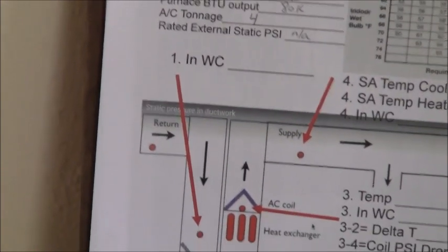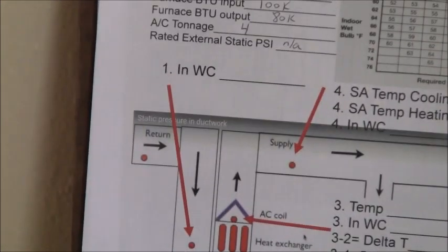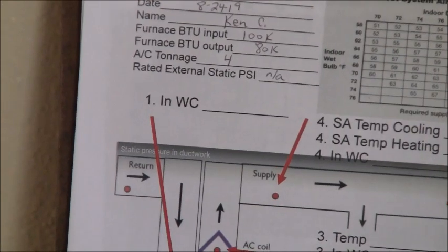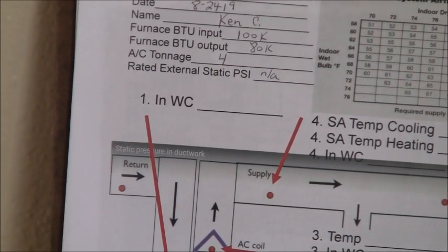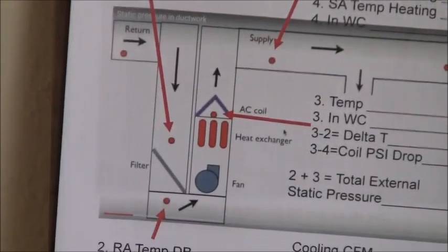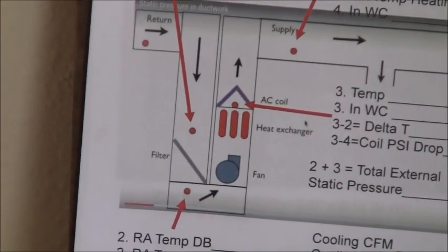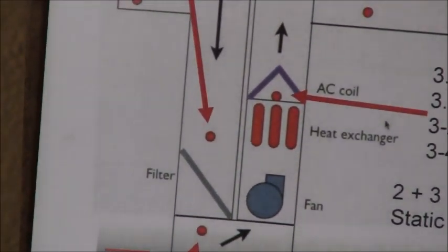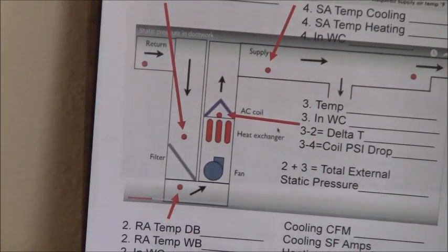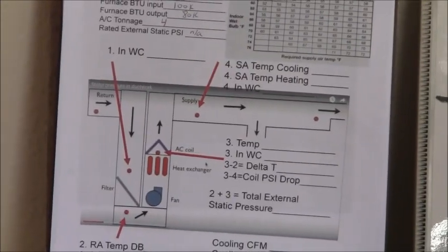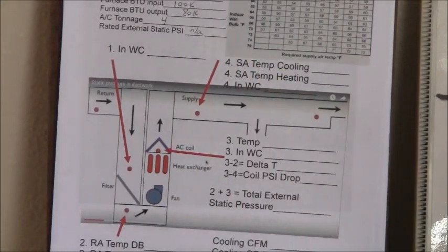This first sample point, just before the filter on the return duct, is point number 1, and inches of water column is how much static pressure is at that location before the filter. I'm trying to determine exactly what's going on in the ductwork and how well this system is breathing.